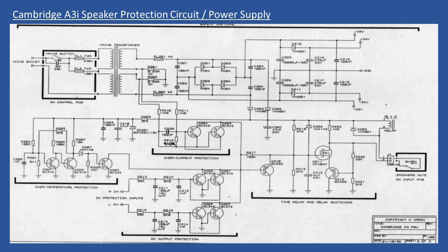And normally if you take the lid off them or the top cap off them, you can see the contacts and they're blackened, and then what you can do is start to clean them and remove that oxide and try to restore them. But if the contacts are pitted and worn, then the only thing you can do is replace the relay. But if the relays are sealed, then typically you'll get a little bit more longevity from that relay type, because it's a vacuum seal inside, you can't remove the top, and it just provides additional life.